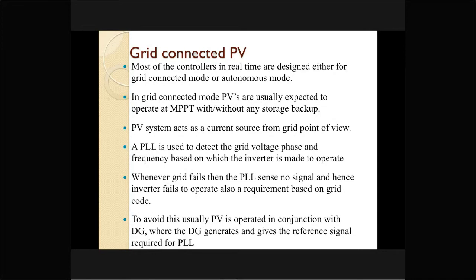Therefore, at many big industrial entities or hospitals and some other business platforms, we go for a diesel generator set, which needs to be operated in parallel with the photovoltaic to produce the reference signal, and the photovoltaic system gets synchronized with the diesel generator. This gives us a benefit in diesel consumption, and in the long run it becomes very cost effective. So the grid connected photovoltaic system, in the real sense of grid, now becomes a virtual grid connected photovoltaic system, where the diesel generator acts as a virtual grid.